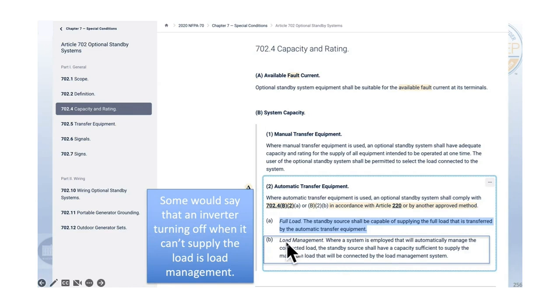One way of looking at that is your standalone inverter sort of does load management in a way, because if it cannot supply the loads, so you turn on the whole house, the way that it does load management is it turns off the inverter. As you know, any standalone inverter, if you try to take more power out of it than it can supply, it turns off. So we can call that load management. But we get into a tricky area here when we call something an automatic transfer switch.